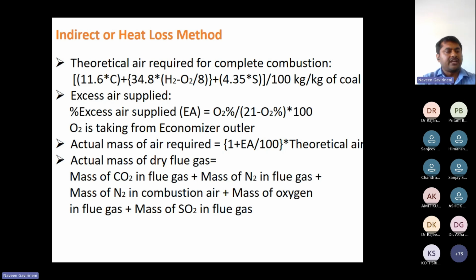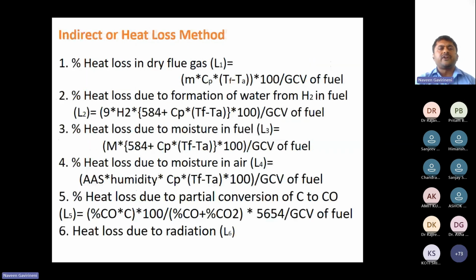Actual air: now we need the mass of actual air. So 1 plus excess air by 100, into theoretical air. There is also a calculation of the dry flue gas. This formula is lengthy, but if you want to minimize it, you just add one to the actual air. Suppose you are getting 12 kg, you can add plus one because it is not more than 1 kg of dry flue gas loss. So 13 kg is the dry flue gas loss. So these are the different types of losses as per the formula it is designed.